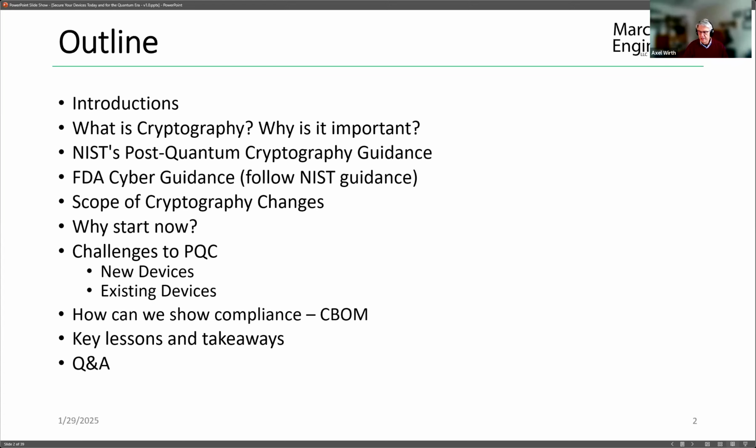And we are certainly keenly aware that FDA recently has started to raise the bar on cybersecurity, and is now specifically looking into a device's security properties as part of the market approval process. And we have seen many devices where market approval was rejected or delayed because of cybersecurity questions. And we'll talk through a couple of examples actually in the course of this presentation.